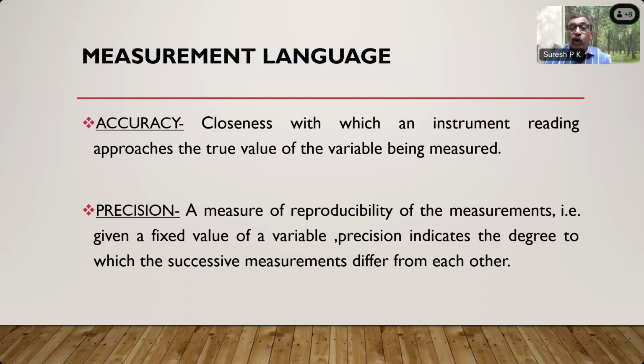Again, the problem is, if you have an instrument which is more accurate than the RRSL instrument, it will be difficult for you to claim more than the accuracy which RRSL has. Or FCRA has. If FCRA has a flow measuring system with 0.25% accuracy, then somebody with 0.05% cannot claim that unless FCRA or RRSL has the capability to verify. So it is required to closely monitor the measurement systems and upgrade them wherever possible.